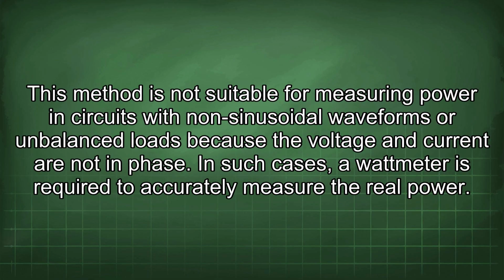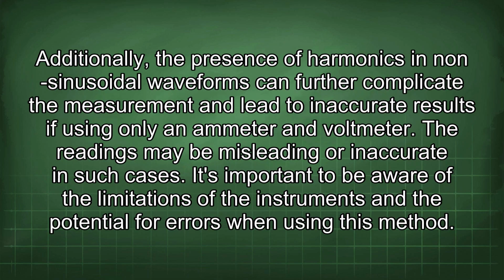This method is not suitable for measuring power in circuits with non-sinusoidal waveforms or unbalanced loads because the voltage and current are not in phase. In such cases, a wattmeter is required to accurately measure the real power. Additionally, the presence of harmonics in non-sinusoidal waveforms can further complicate the measurement and lead to inaccurate results if using only an ammeter and voltmeter. The readings may be misleading or inaccurate in such cases.